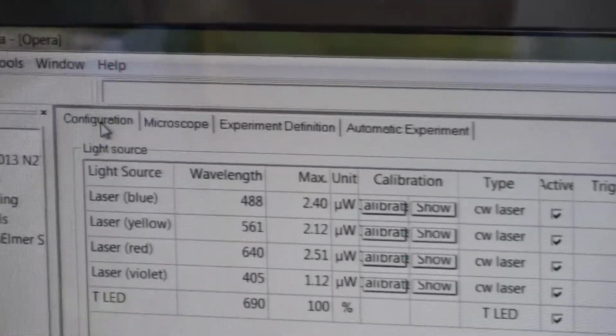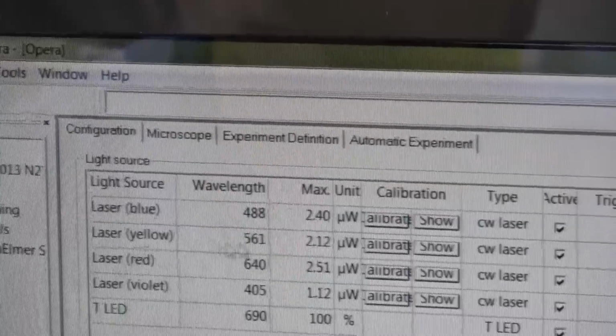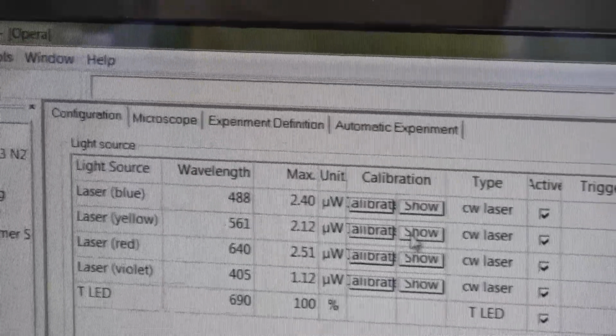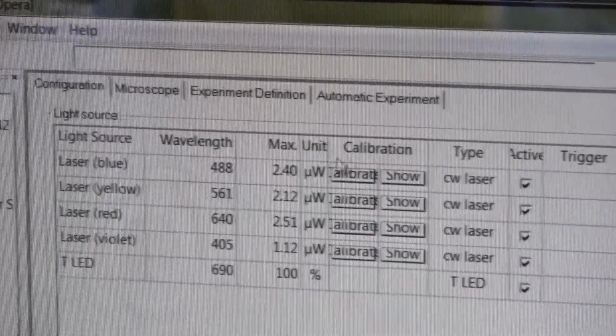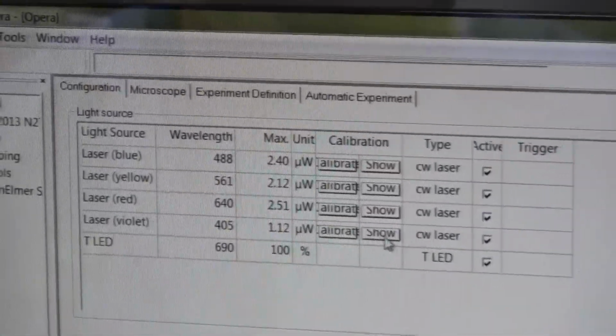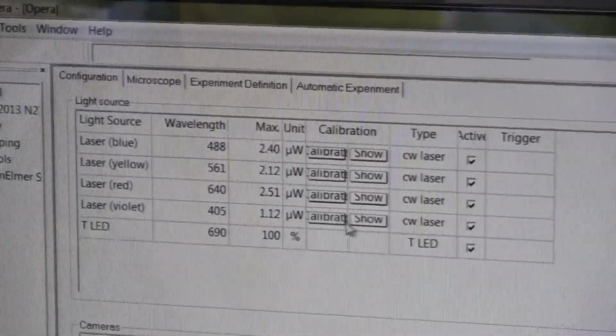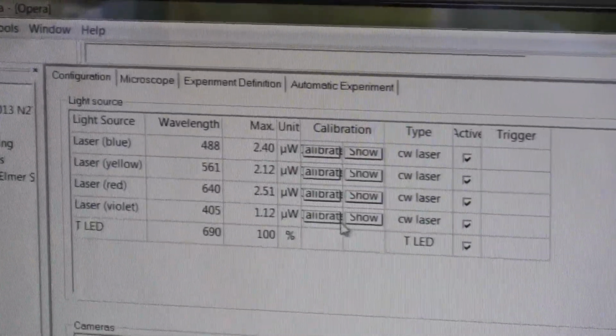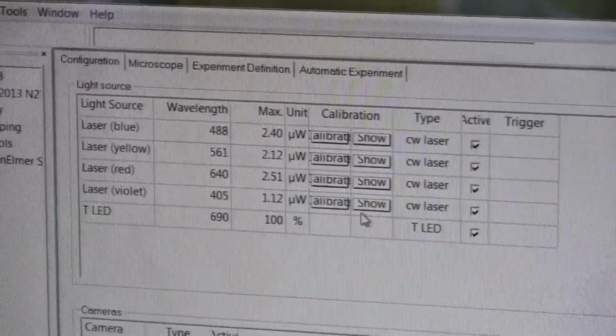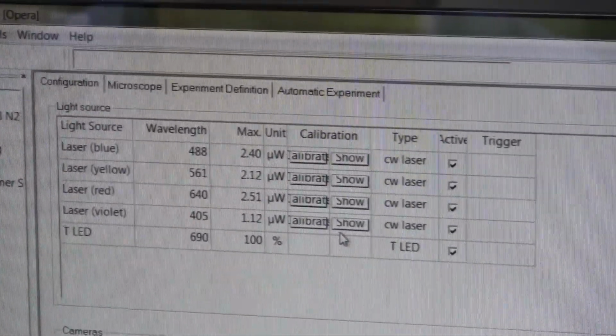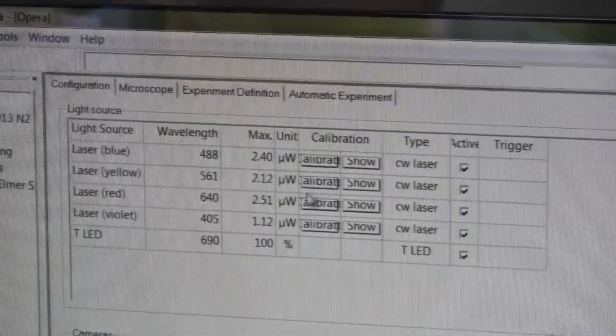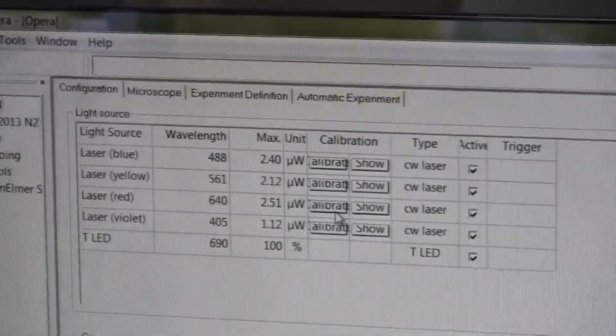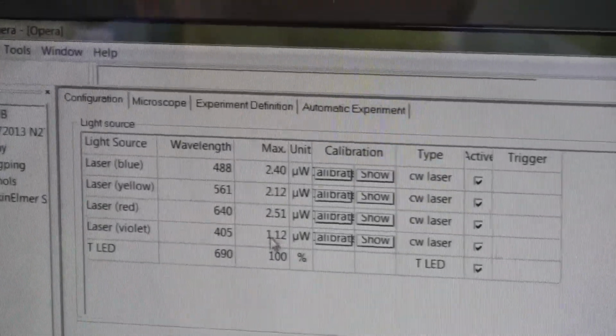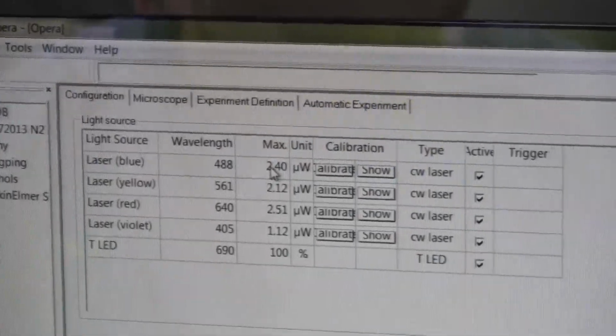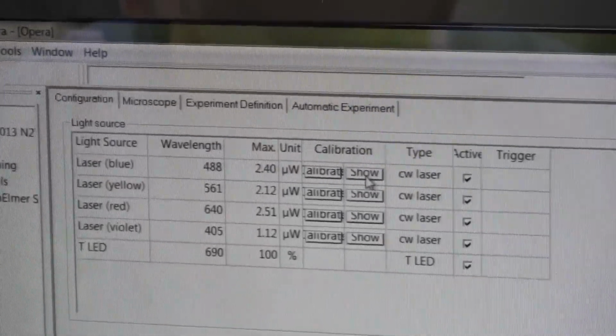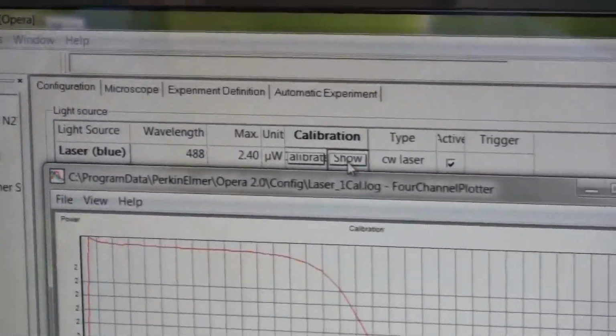The configuration tab is the one we're on now. That gives you all the lasers. And actually I'm going to show you the calibration numbers here. Now I have not calibrated the lasers, and the reason is that once it's moved into the last position where it needs to be set up, then the calibrations need to be done on the lasers. Right now they're still doing pretty good. They're all still within perfectly good range, and you can see some of the calibrations here.